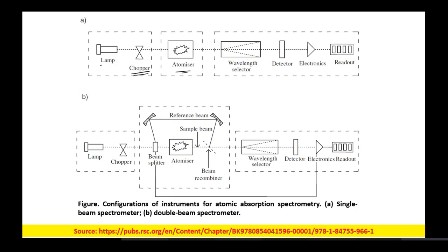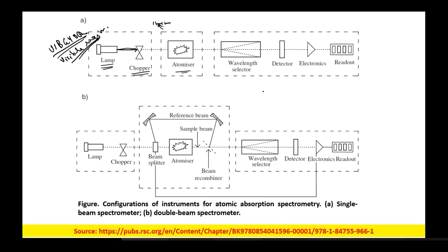When the lamp generates light in the VIBGYOR region — the visible region — you get a continuous spectrum. What does the chopper do? For a particular period of time it sends the light, then stops the light band, then sends it again. During the stop time, it records the signal, enabling it to stop the lamp glare from being recorded in the detector.